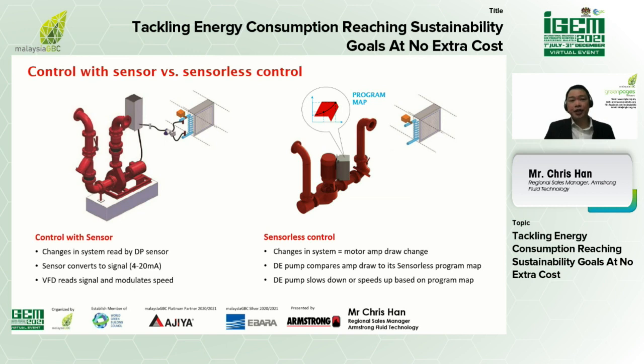So during operation, as the two-way valve opens and closes, the changes in the system pressure are read by the DP sensor, or the differential pressure sensor, and then the sensor converts that signal to a 4 to 20 milliamp reading. Thereafter, the variable frequency drive will take that reading and modulate the speed up and down, speeding up or slowing down the pump based on the signal it is receiving from the differential pressure sensor. And this is what I believe most of us are very attuned to, very familiar with.